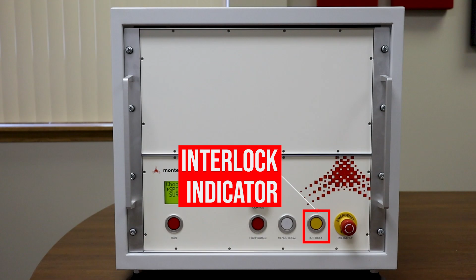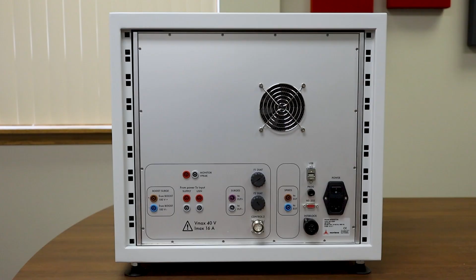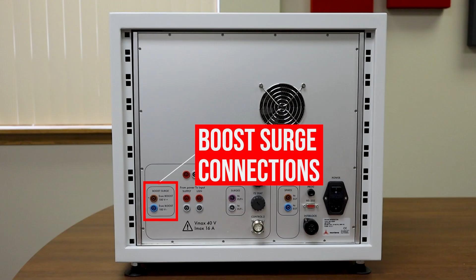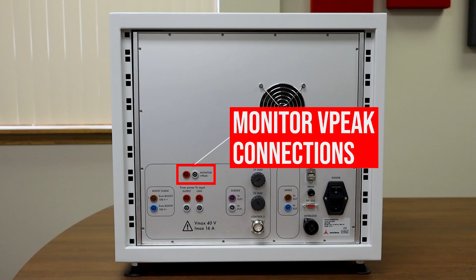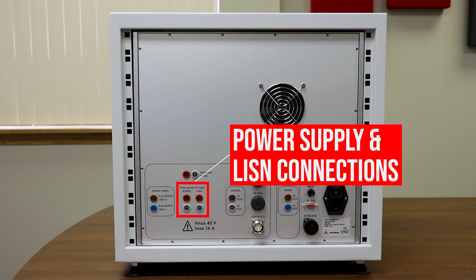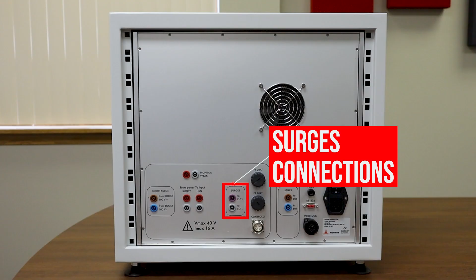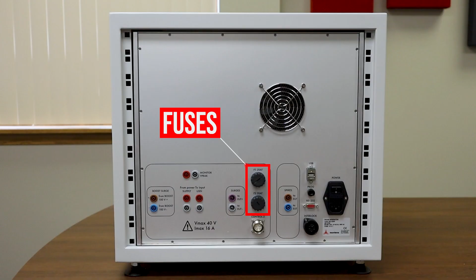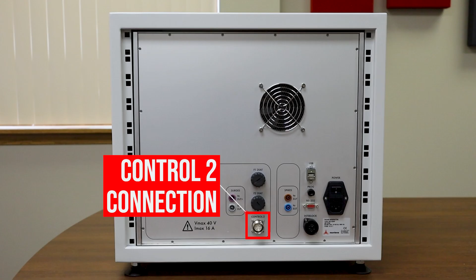Let's get the system turned around and take a look at the back. Here's the back of the PG1275F. Let's start from the left at the lower corner and work our way right. On the far left, we have the boost surge connections. As we work our way right towards the top of that section, we have the monitor Vpeak connections, and below that, the connections from the power supply and the inputs on our LISNs. Next to that, we have the connections for the surges to the equipment under test. And then to the right of that, we have our fuses, which are labeled F1 and F2, and our Control 2 connection. The Control 2 connection will be used with the external DM400 diode.